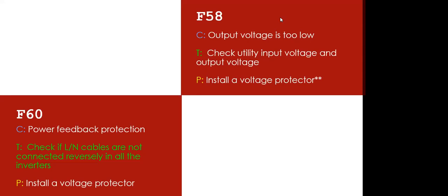So before this becomes an error, definitely it takes a longer time before you know. And if this happens, it will really damage the parallel card section. Majorly, it will damage the control card, if you don't notice it in time.